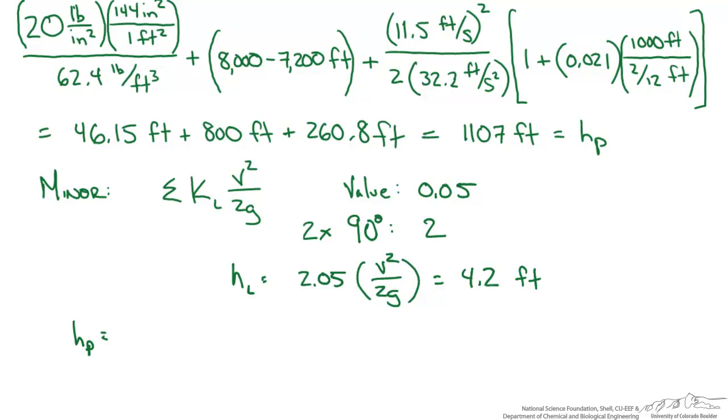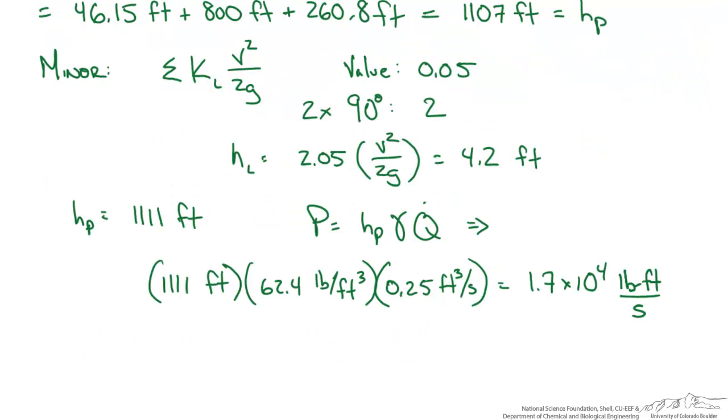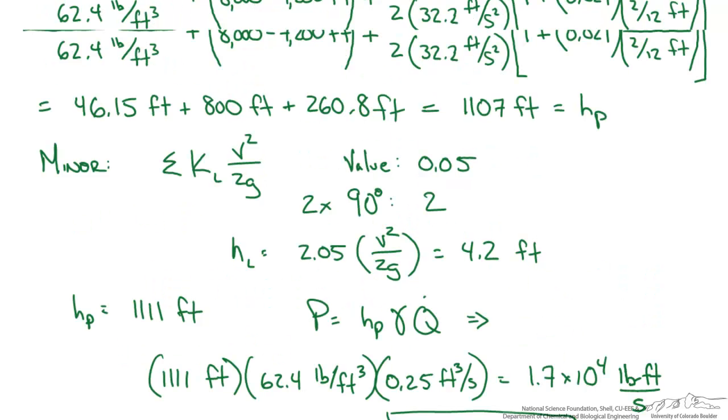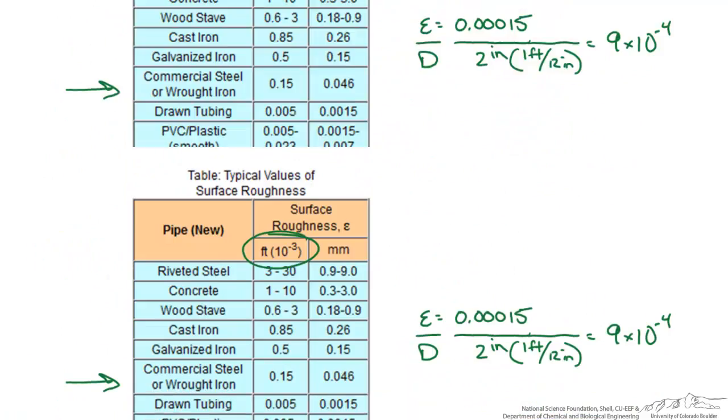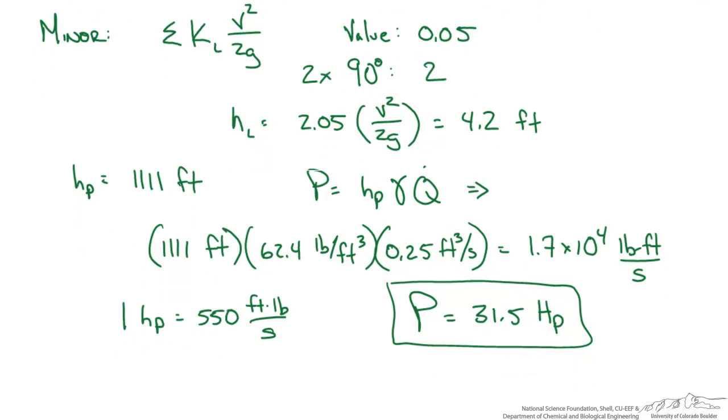We could account for this just to be more accurate. Our total shaft head necessary from the pump is about 1,111 feet. We put this into our equation for power, which shows that the shaft head multiplied by the specific weight of the fluid and volumetric flow rate gives us 1.7 × 10⁴ pound-foot per second. Converting to horsepower, our total pump power is 31.5 horsepower. We go back to our original problem statement and can safely say we've calculated the power added by the pump.